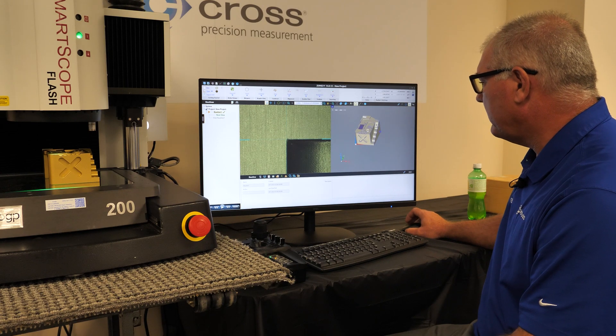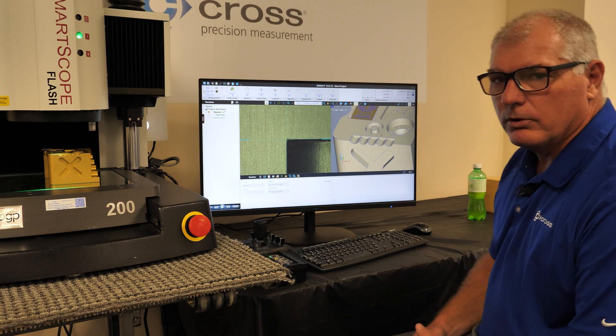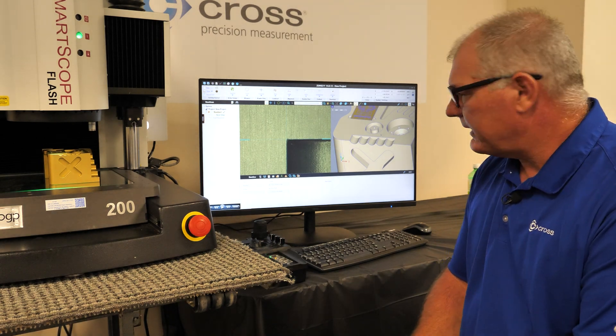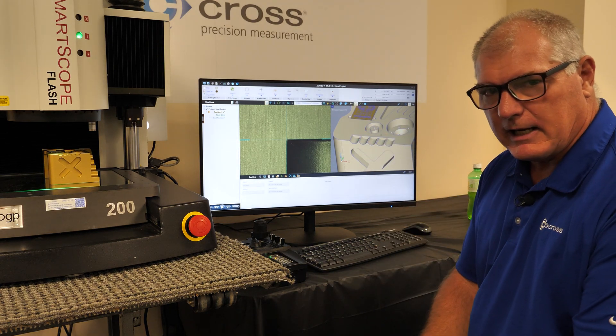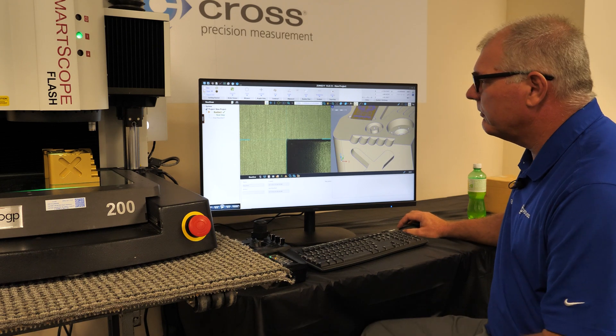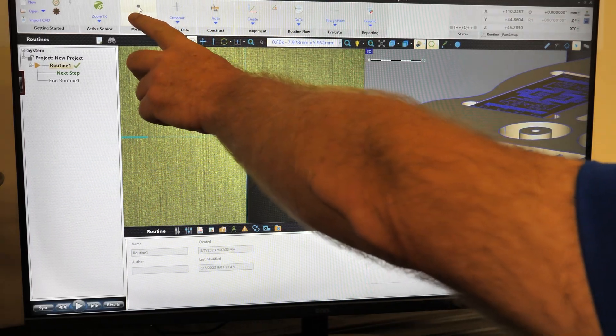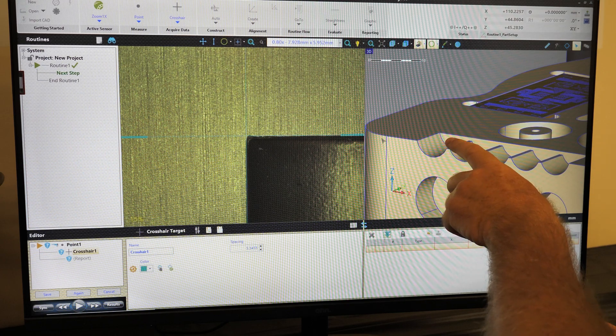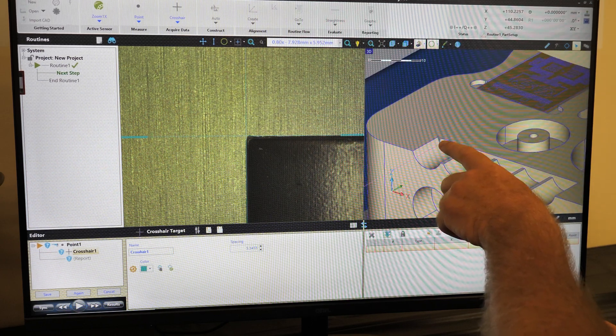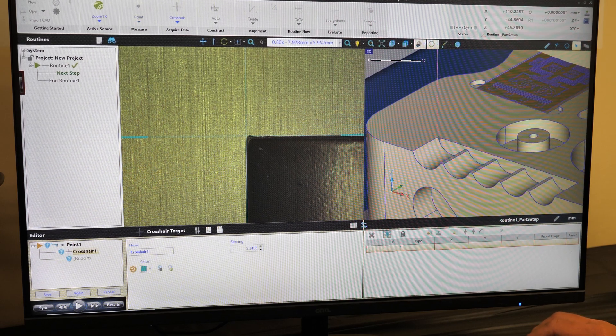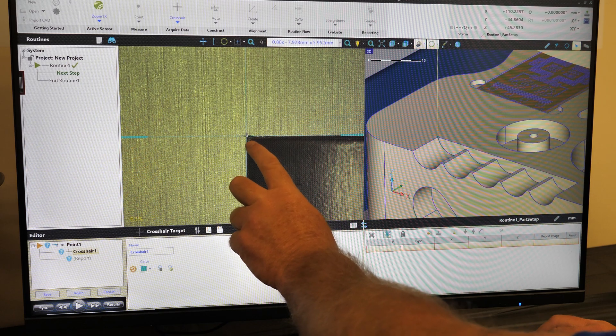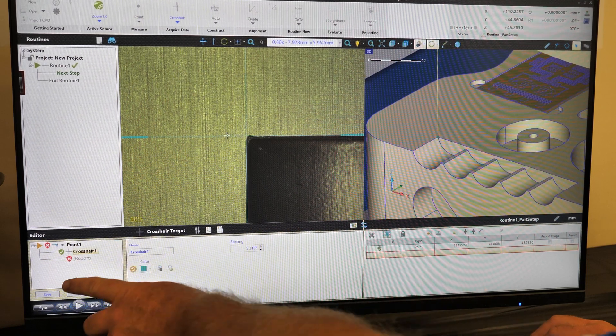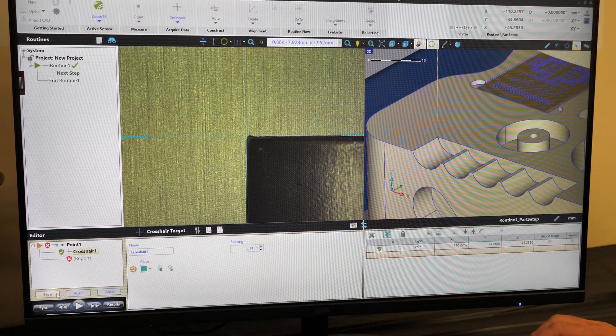I'm going to zoom in on the training part and look for a corner — one point where I can say this is where I want to start from. In this case, I'm going to use the corner of one of these scalloped cutouts. To do that, it's simply just three clicks: we select our point, the tool we want to use to measure — in this case a crosshair — and then we select the CAD model to associate. As we bring the mouse over the CAD model, it's going to snap to that intersection point. We simply click there to identify it, then click on the part itself, and then select Save. Those two points are now associated together.